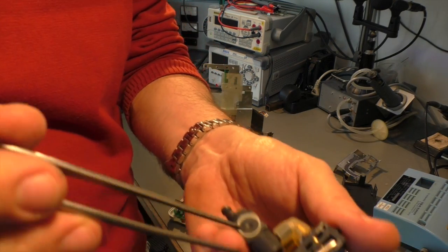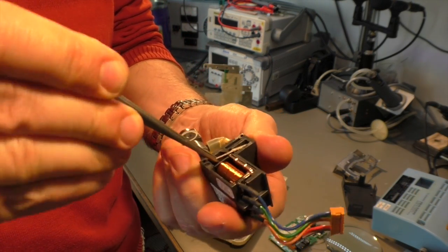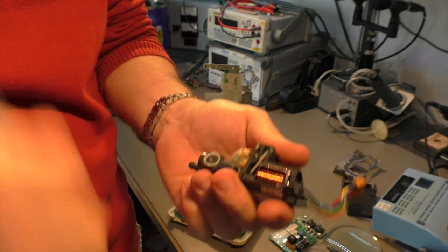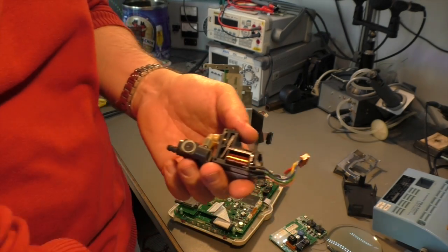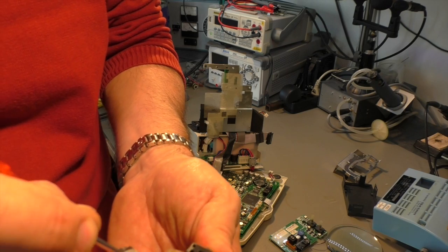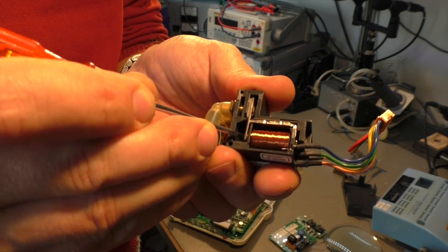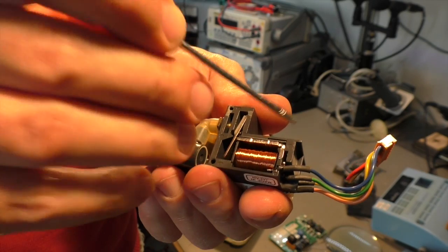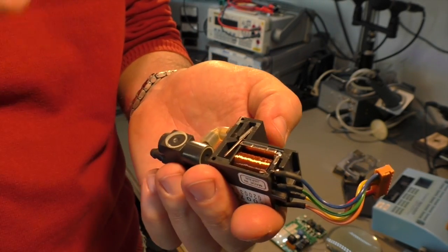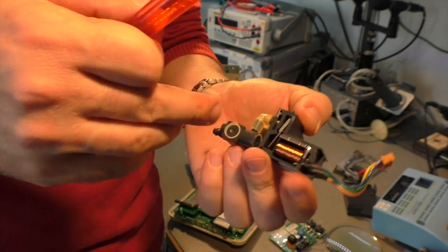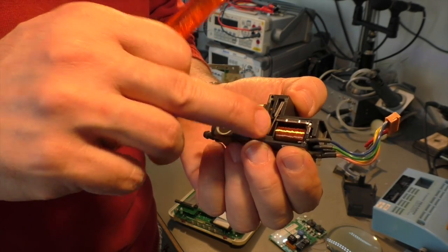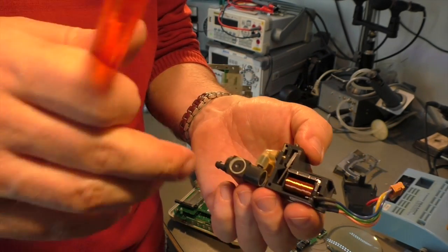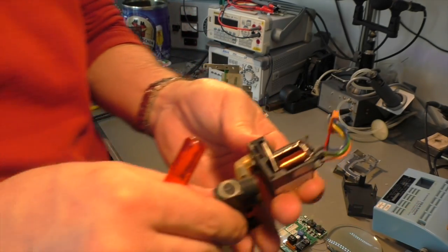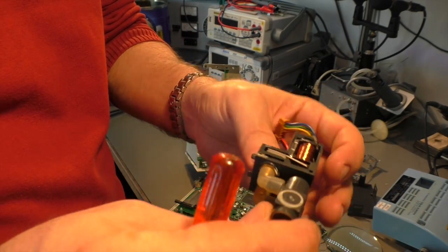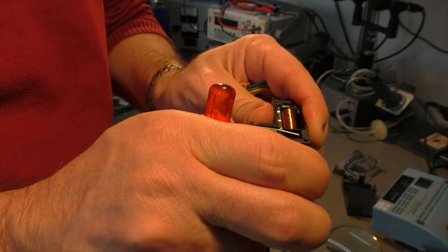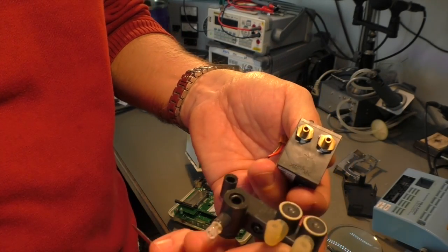Let me see if we can take that out. Not that easy. So you just have to trust me that I think it closes when it's energized and opens, so all the air will escape here, and the pump pumps air in. This one here opens to release the pressure, because you have to release the pressure after the measurement, or your patient will probably lose its arm because the blood is not circulating anymore.